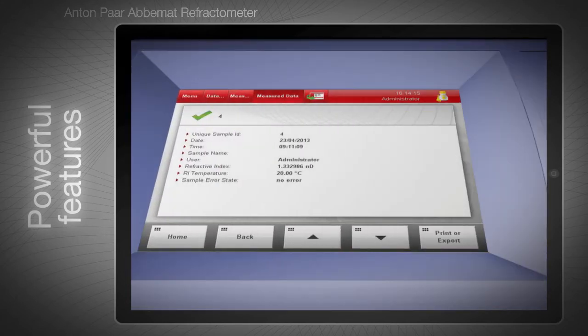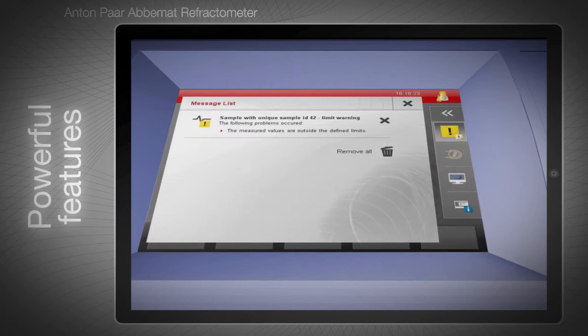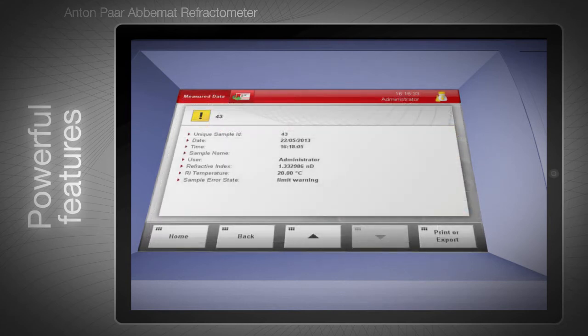Abbemat Performance Plus line models give you a limit warning if your readings exceed defined limits. This warning is recorded in the data memory together with the measured data.